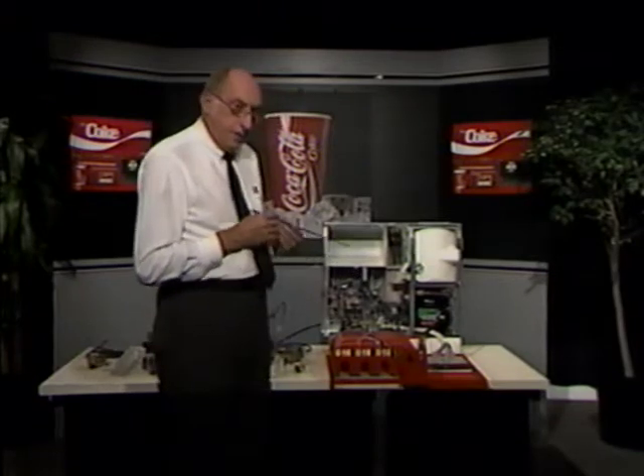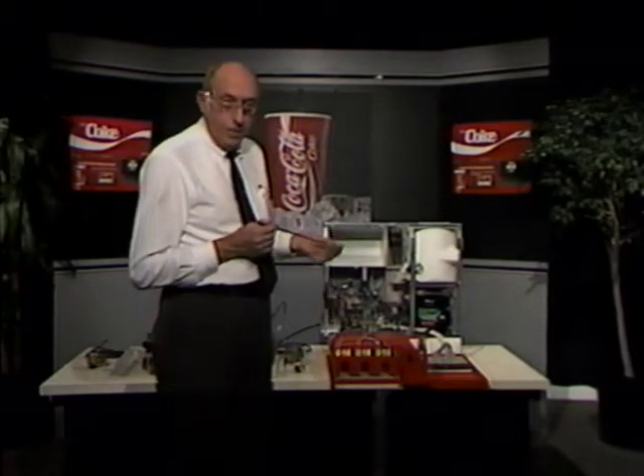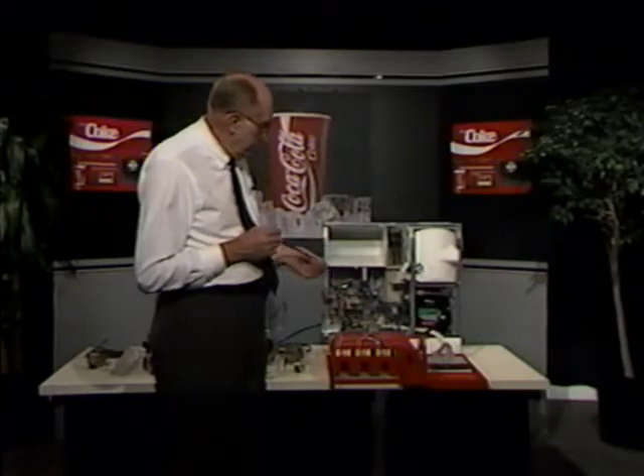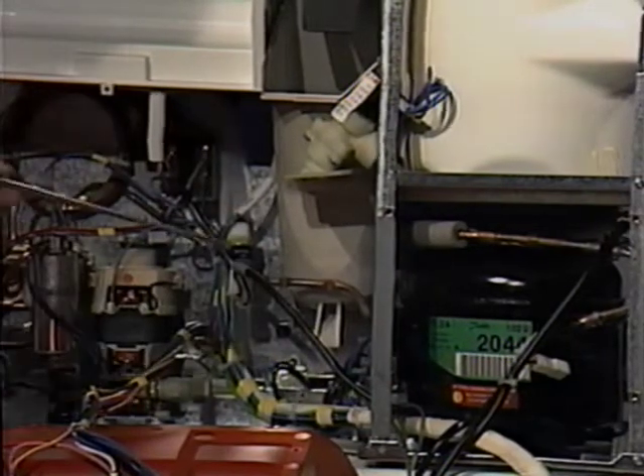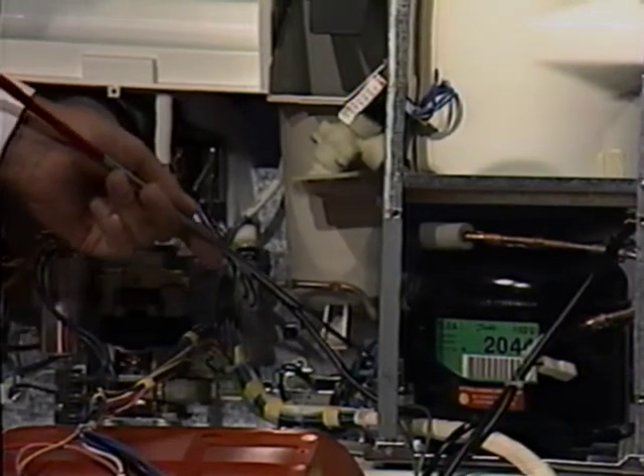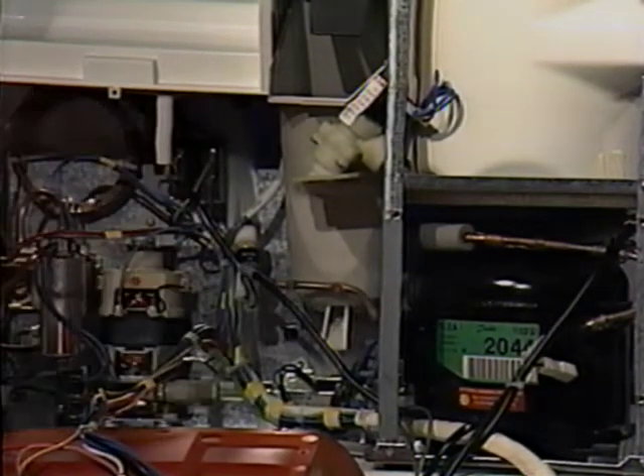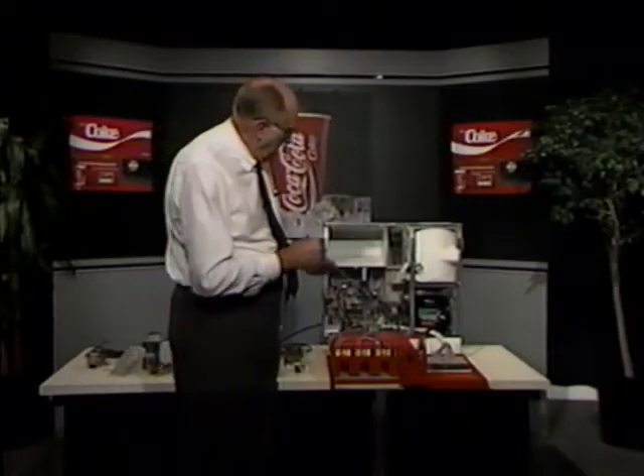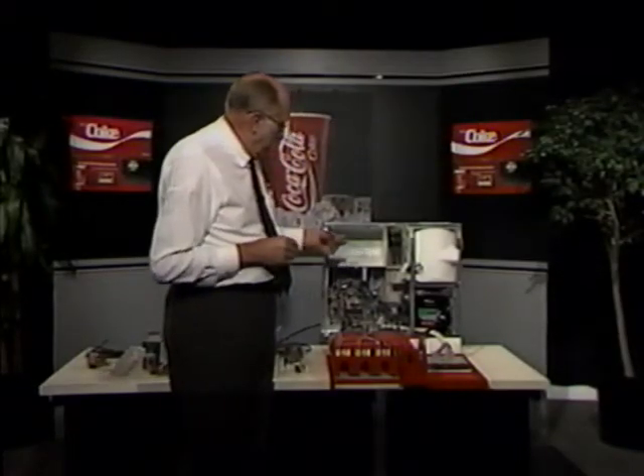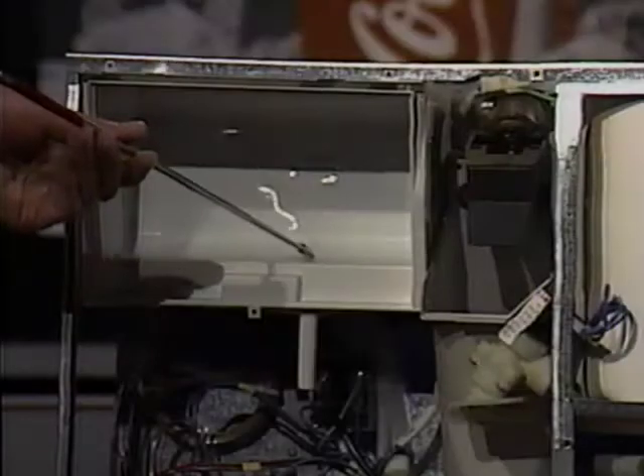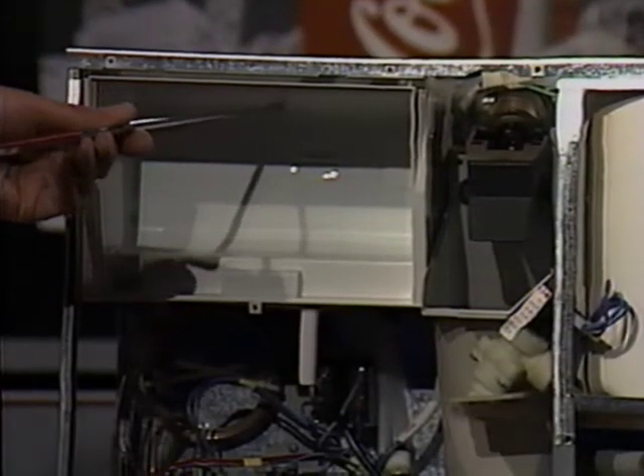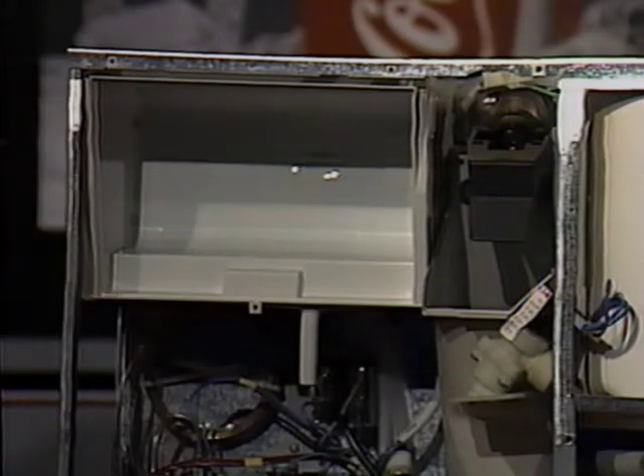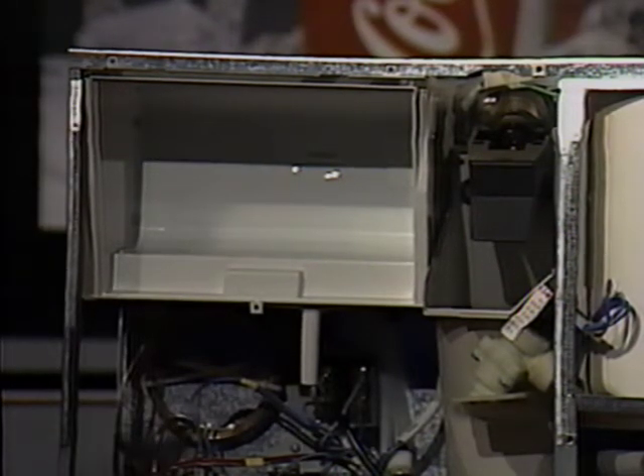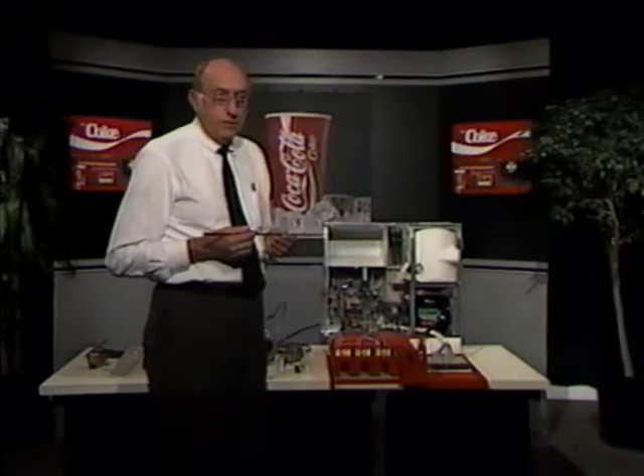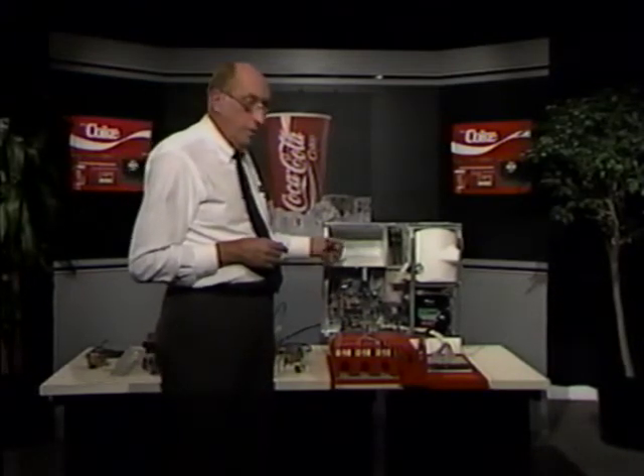The compressor, as with almost all compressors, has a starting relay. That's located on the side of the compressor. It's removable for servicing, and the connections to the compressor are located on the side. The syrup compartment evaporator is this white lining inside the syrup compartment. Now, under normal operations, moisture condenses on the walls of the syrup compartment evaporator.